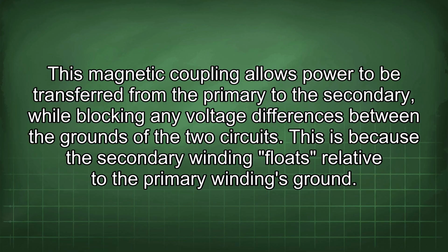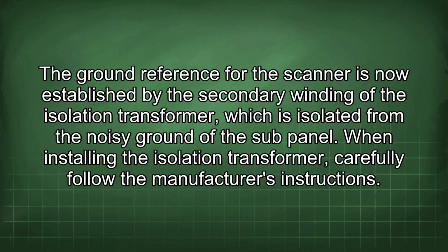This is because the secondary winding floats relative to the primary winding's ground. The ground reference for the scanner is now established by the secondary winding of the isolation transformer, which is isolated from the noisy ground of the subpanel. When installing the isolation transformer, carefully follow the manufacturer's instructions.